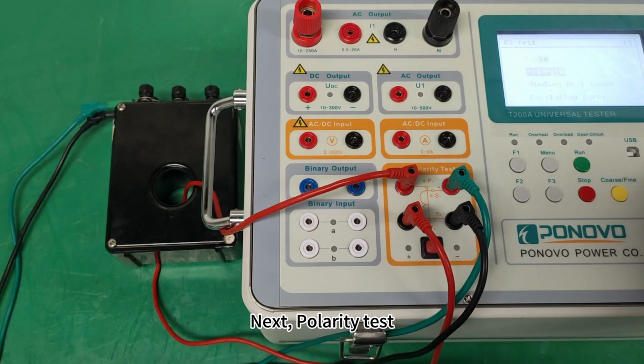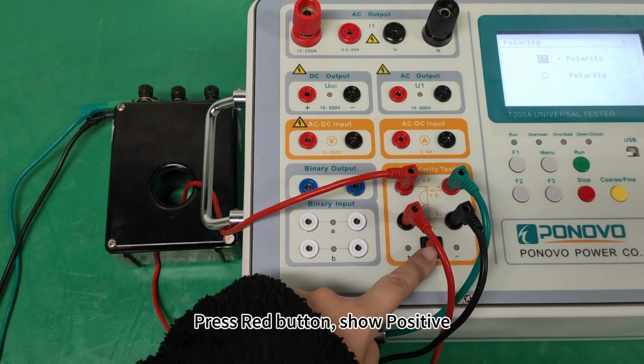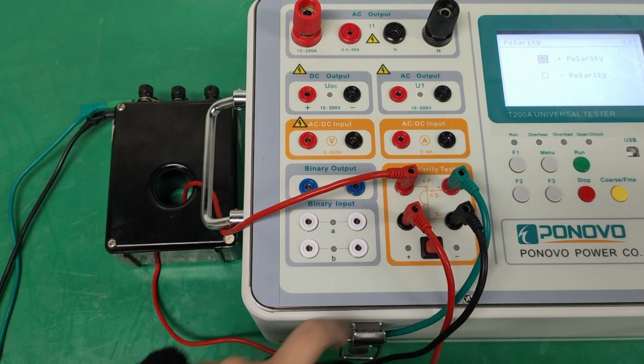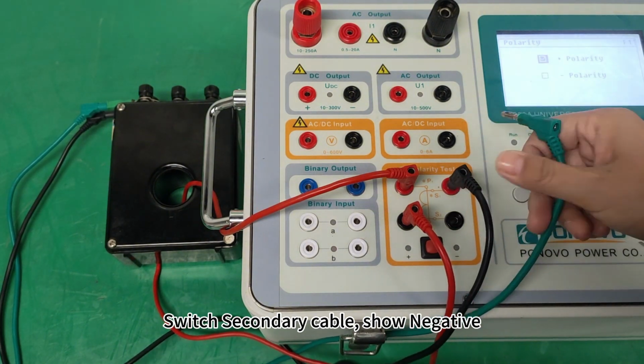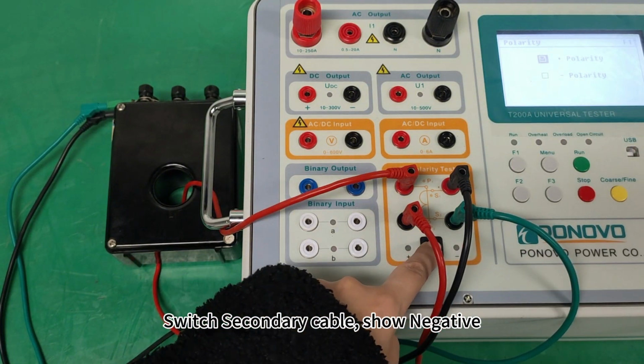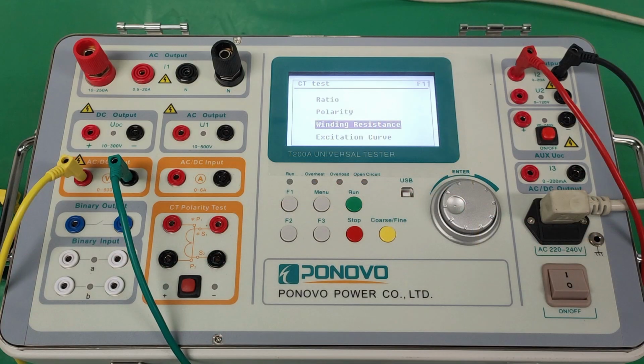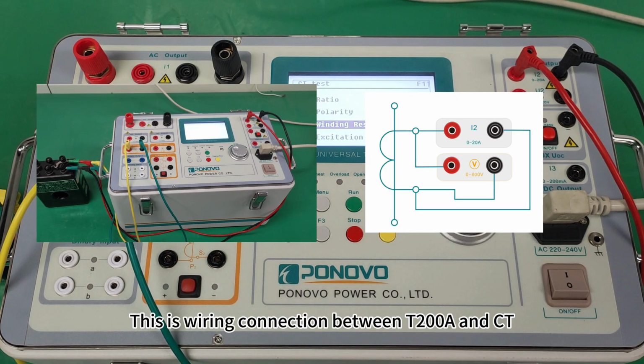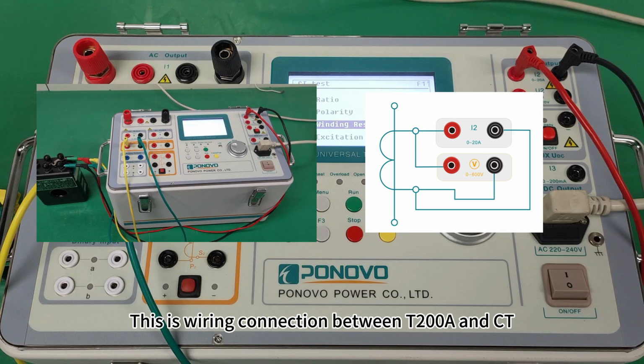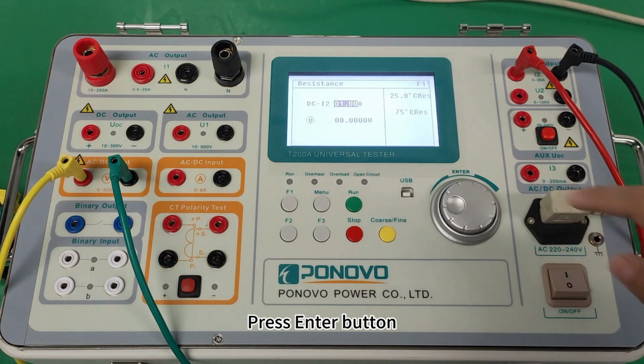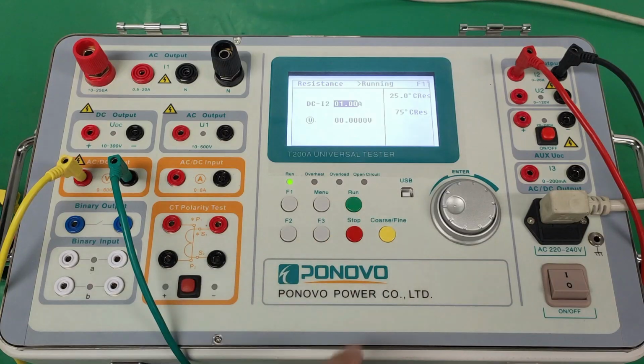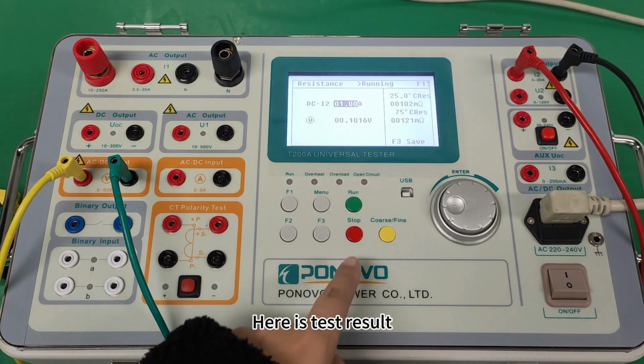Next, polarity test. Press red button, show positive. Switch secondary cable, show negative. Next, winding resistance test. This is wiring connection between T200A and CT. Press Enter button. Press Run button. Here is test result.